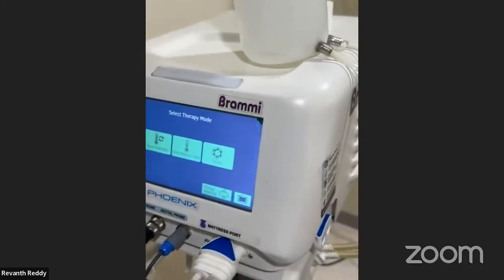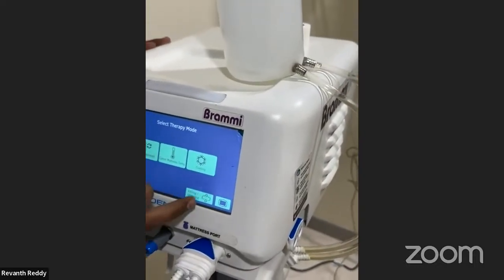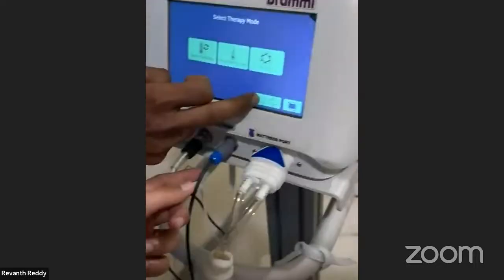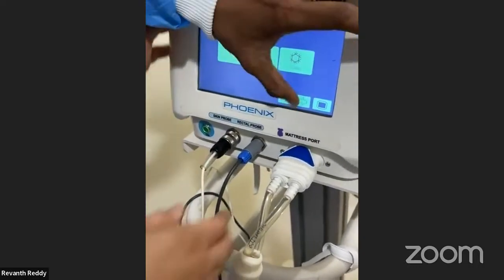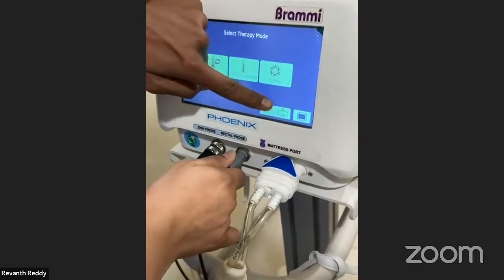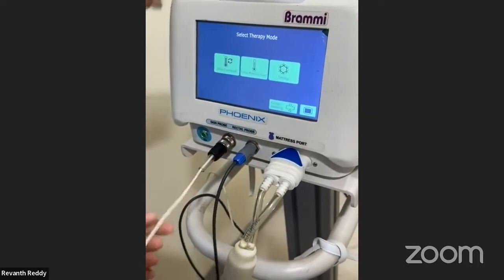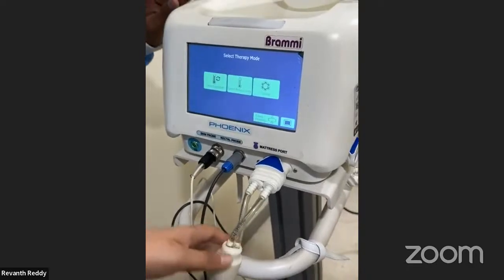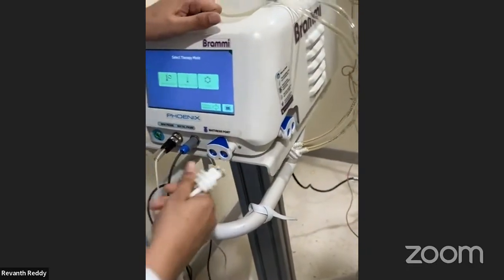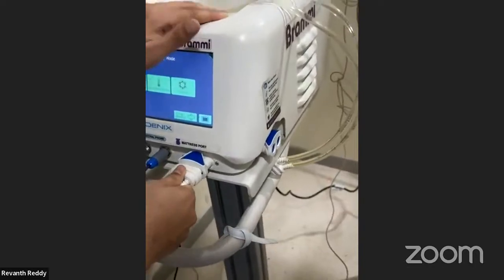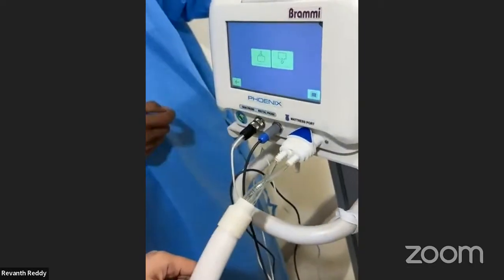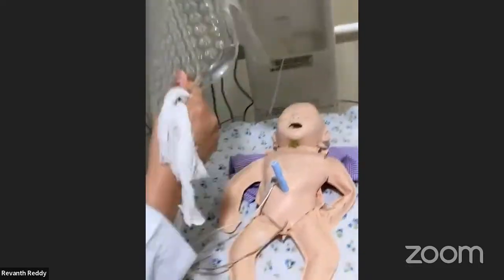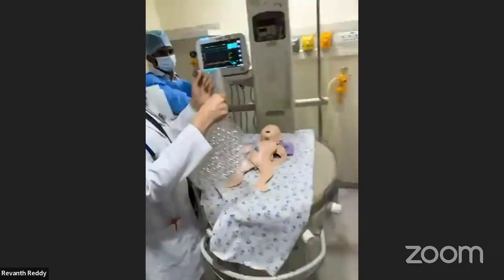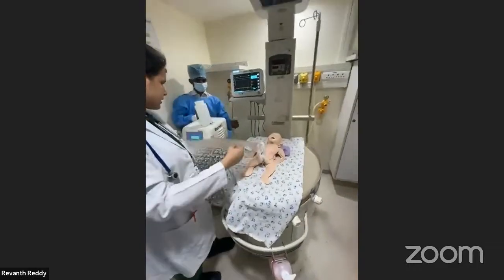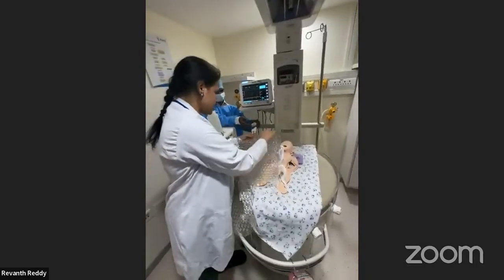So basically, when we start with the device, you have the rectal temperature probe as well as the skin probe here. So the rectal probe can be easily fitted. This must be connected to the baby's rectum. This also has a skin probe. This is the provision for the insertion of the coolant liquid that reaches the baby through this tube, and this is connected to the mattress. So you can see the mattress here with the coolant, water-based coolant that is circulating through the mattress. So this is connected to the device using these probes.